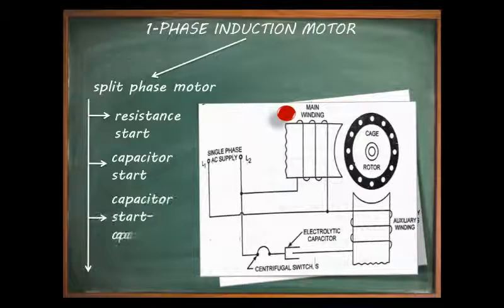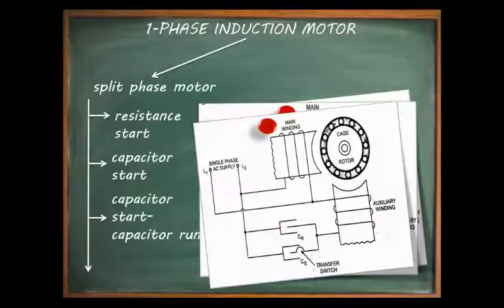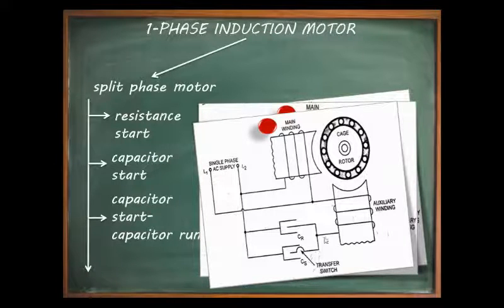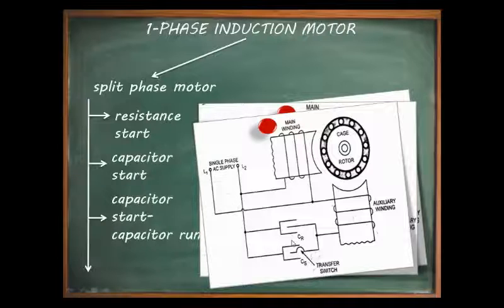The third type of split phase induction motor is the capacitor start capacitor run single phase induction motor. In this type, two capacitors are used — CS (starting capacitance) and CR (running capacitance). The CS is connected with the centrifugal switch and is removed from the circuit once the motor picks up speed, but since CR remains connected, the motor is called capacitor start capacitor run.